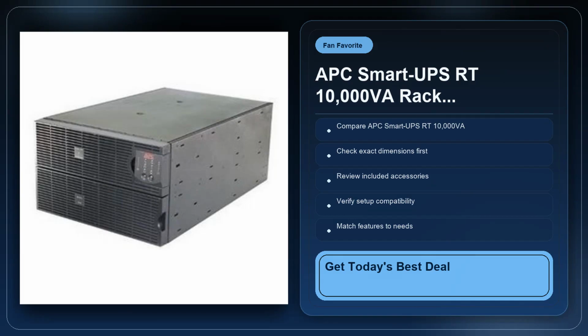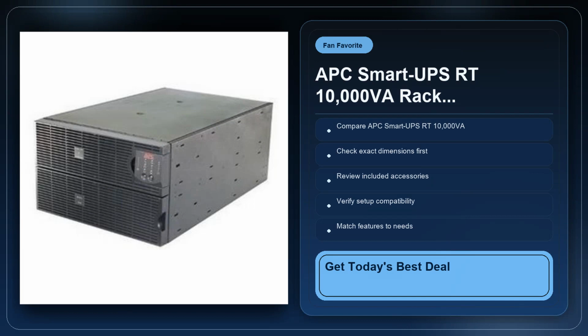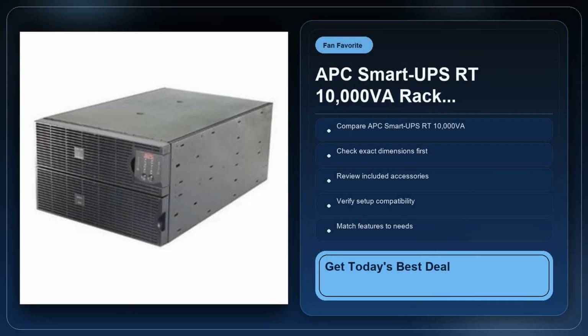So, who should buy? If you're managing a rack with a 4 to 6 kilowatt load, need hot swap batteries, run on 208V 3-phase power, and have a maintenance plan for battery replacement, the Smart-UPS RT 10000 VA checks most boxes. It gives you the scalability to add more servers later without having to replace the UPS, and the network management features integrate smoothly with most monitoring stacks. If you're a small business that's just getting started, a lower capacity UPS will likely serve you better and keep your capital expense lower. Who should skip it?